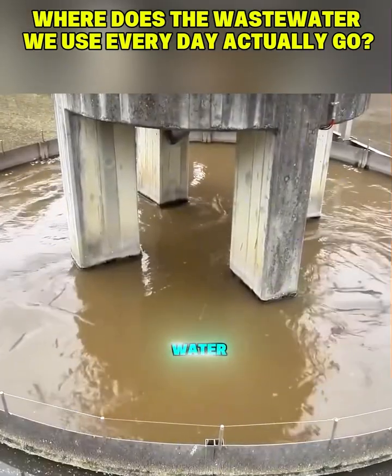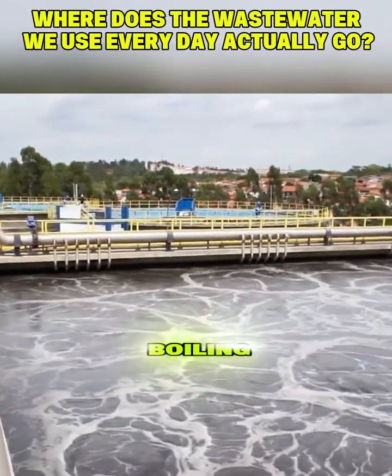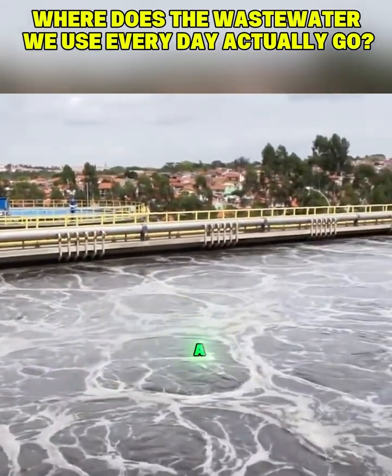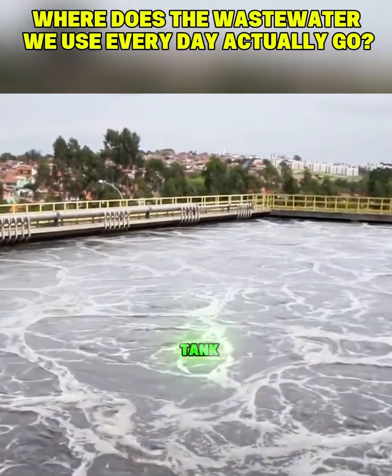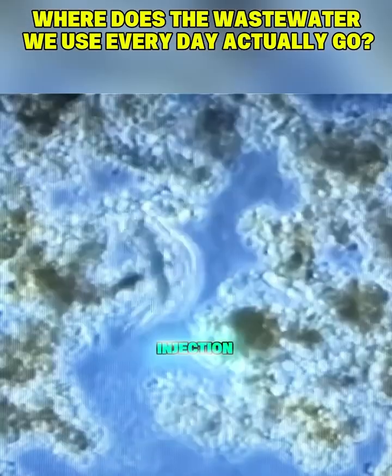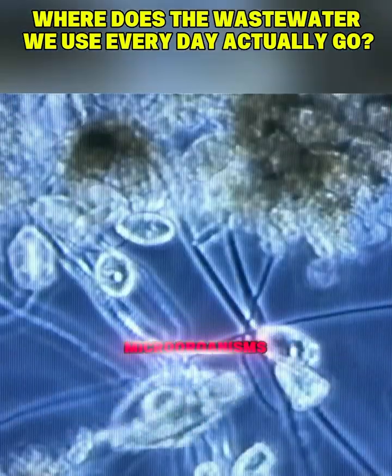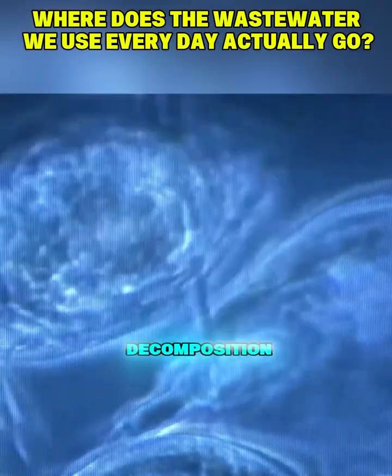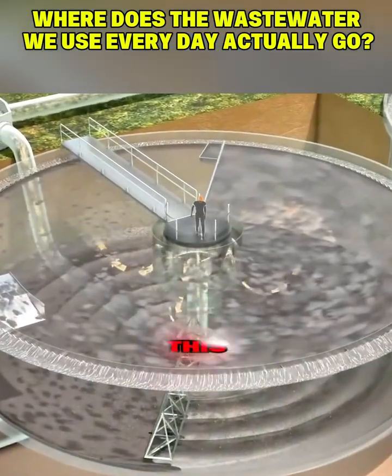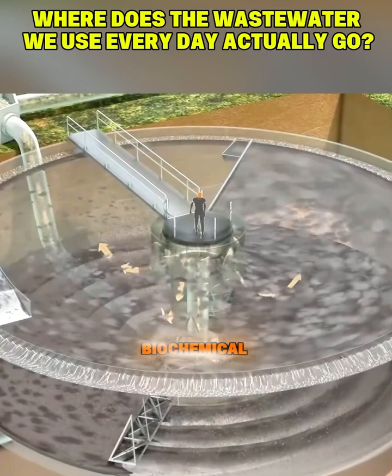You can see the water vigorously bubbling. This is not boiling, but rather the injection of a large amount of oxygen into the tank. The purpose of oxygen injection is to activate the microorganisms in the water, accelerating the decomposition of organic matter. This process is known as biochemical degradation.